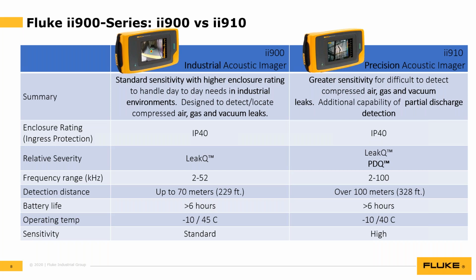Additionally, the 910 is specifically designed for partial discharge, so it looks at a wider frequency range, which also helps for leaks, by the way, but partial discharge sometimes falls outside that lower frequency range, so you want a better chance of detecting it. Also, we added algorithms to better analyze the partial discharge. So the 900 might detect some partial discharge cases that the 910 does, but it's not designed for it.